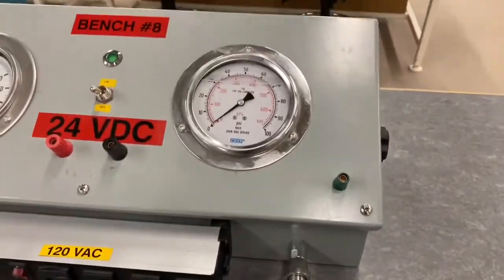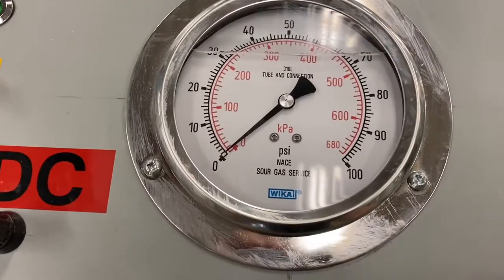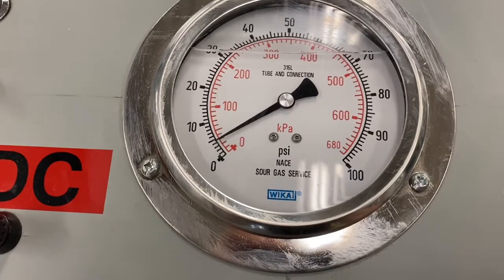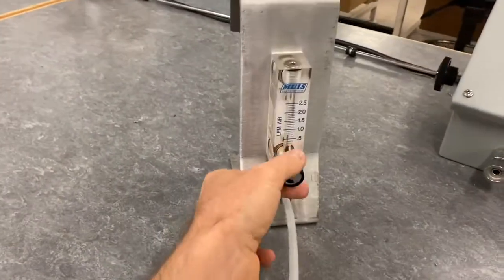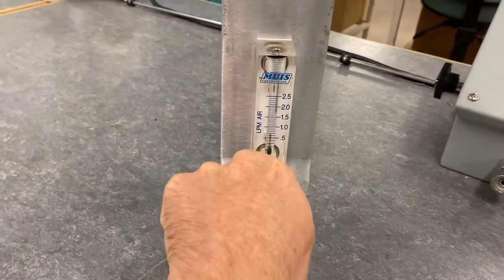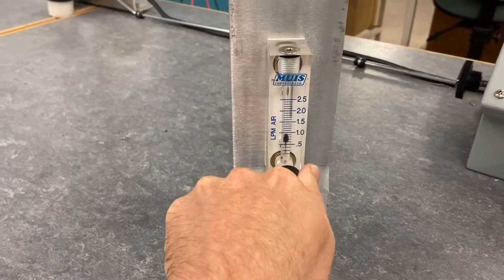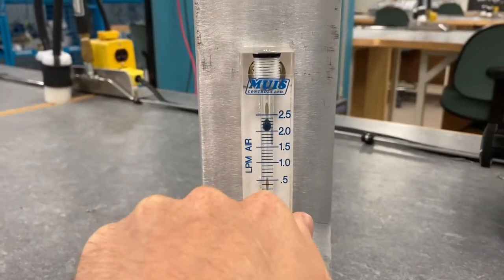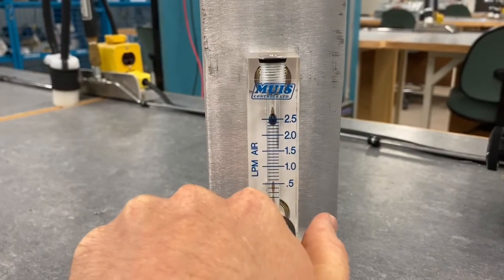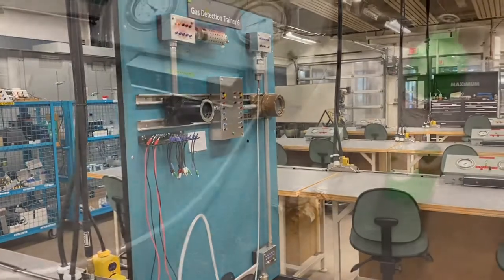I'll increase the pressure here and we should see this gauge pop up to about five PSI. There, about five PSI. If we go over to our variable air meter, it's important to have this shut when we start, because if we have it fully open, it'll fire the ball right to the top quickly. I'll just open this and we'll raise it up. We'll go up to 2.5 liters per minute. We want to make sure that ball is in the center of the line. We have 2.5 liters per minute of instrument air flowing to that sensor right now.